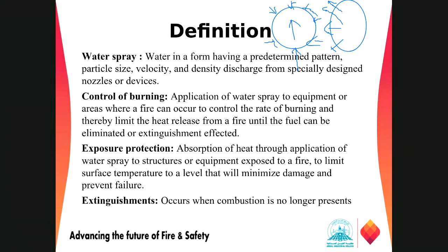So we just want to discharge water to cool this surface. We call it the exposure protection, right? The water will absorb the heat from those surfaces and limit surface temperature to a level that will minimize damage and prevent failure. Because once it has failed, all the liquid will come outside. Maybe gas is there. The gas will be dangerous, maybe poisonous.